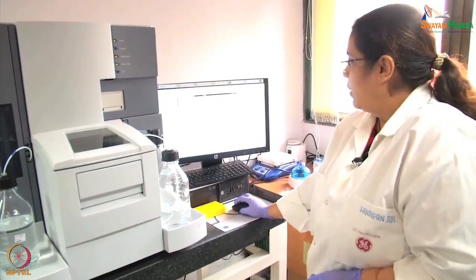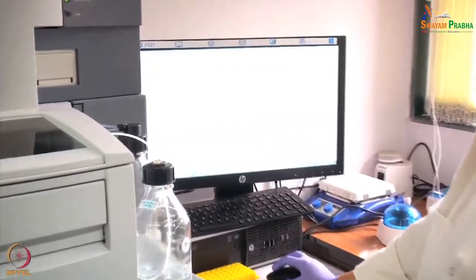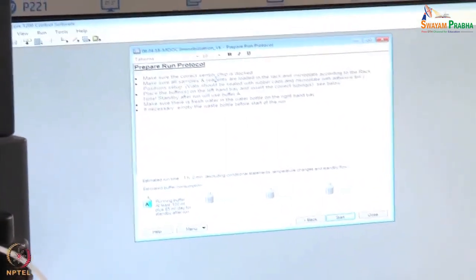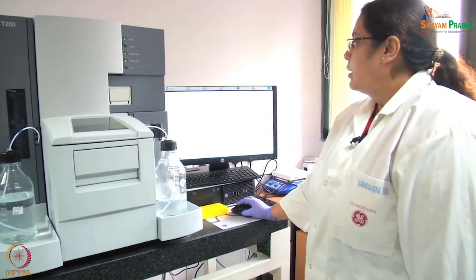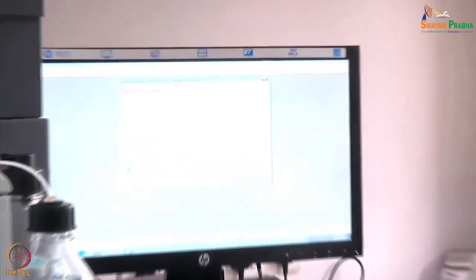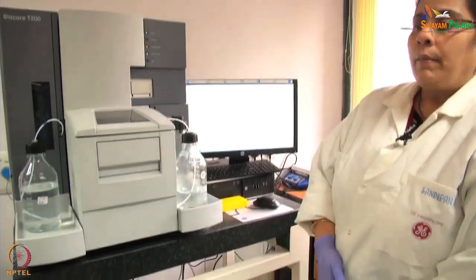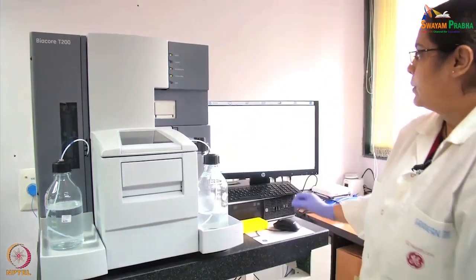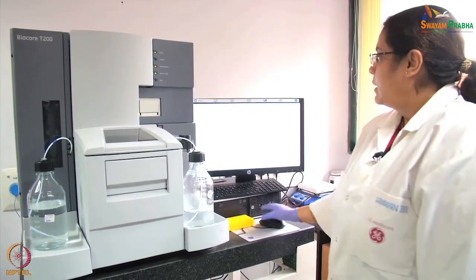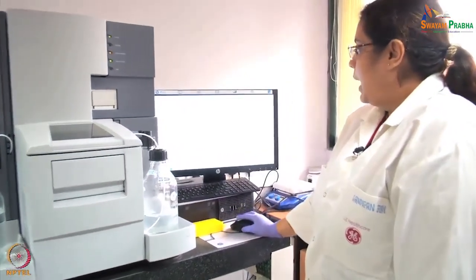Once the insertion of the sample rack is over, you click on next. It gives you a run protocol and you have to follow all of this. At this point you can check whether you have inserted the correct sensor chip and whether all the samples and reagents are in the rack. Make sure the correct sensor chip is docked and all samples and reagents are loaded correctly. Then place the buffer — make sure the correct buffer is in your left-hand side tray and that there is enough buffer for the entire run, the caps are tight, and there are no bubbles. If your waste bottle is full, empty it, and make sure there is fresh water in the right-hand side bottle. Then you click on start to begin your immobilization reaction.